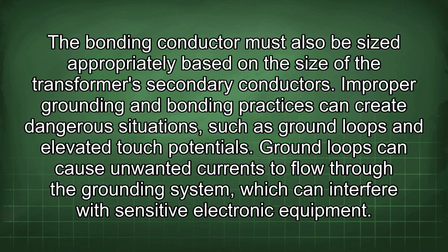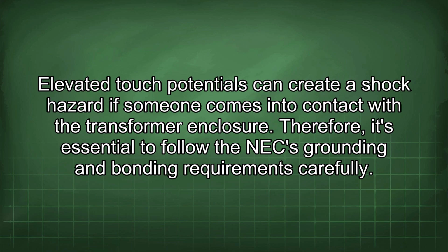Improper grounding and bonding practices can create dangerous situations, such as ground loops and elevated touch potentials. Ground loops can cause unwanted currents to flow through the grounding system, which can interfere with sensitive electronic equipment. Elevated touch potentials can create a shock hazard if someone comes into contact with the transformer enclosure. Therefore, it's essential to follow the NEC grounding and bonding requirements carefully.